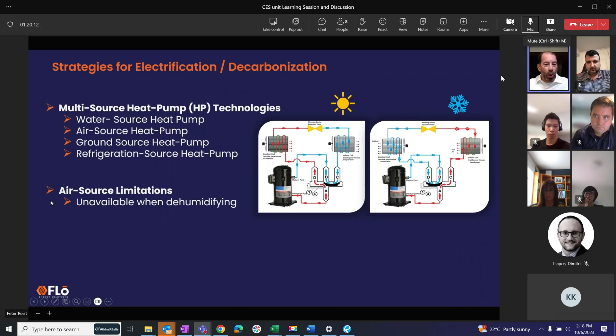Efficiency drops, of course, below 35. We have a great frost problem right around freezing. Frost only occurs 9 degrees above freezing and 9 degrees below freezing. Below that, we don't get frost, not enough moisture in the air, and above that, we're not at cold enough temperatures to frost. And of course, outdoor air units have real big challenges when we're talking about air source heat pumps, just because that cold air coming into the coil pushes us outside of our compressor envelope, and we have to shut down the unit. So that's something to keep in mind.